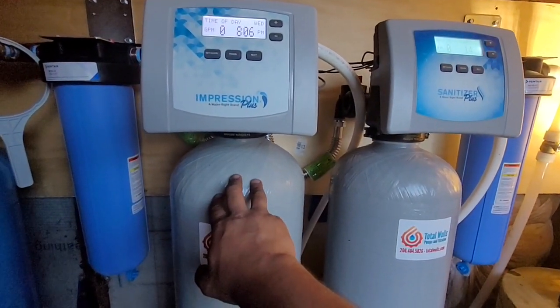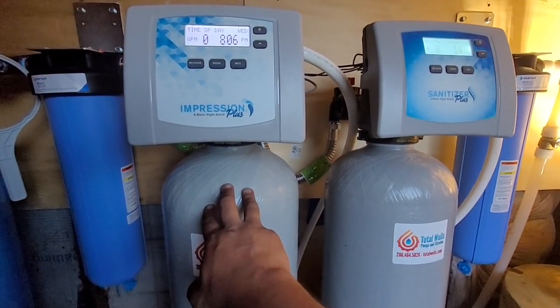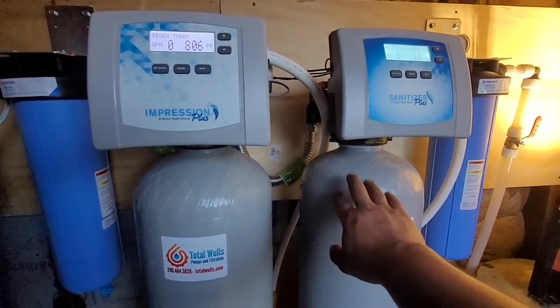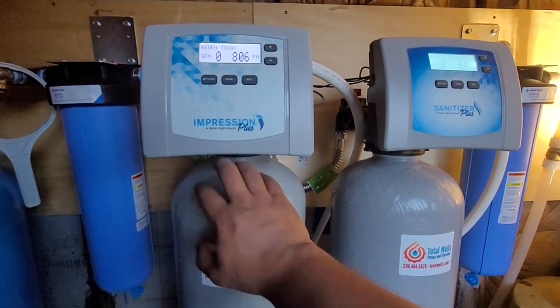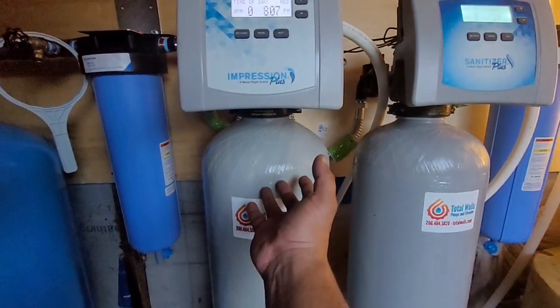Following that, we have a system here — the Impression Plus — that's going to be dealing with any iron that may pass through and any remaining hydrogen sulfide not treated by the sanitizer. During the regeneration cycles for the Impression system, we also have an ozone generator. The top third of the Impression system is a dry cell — an air chamber.